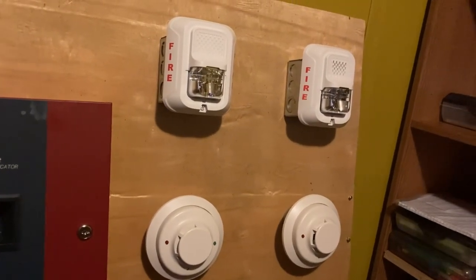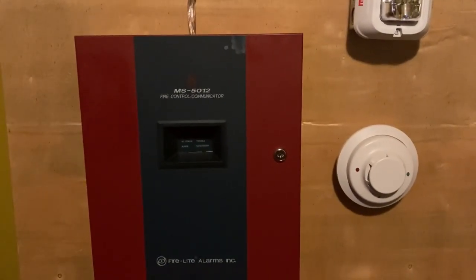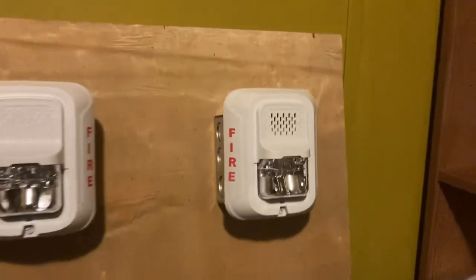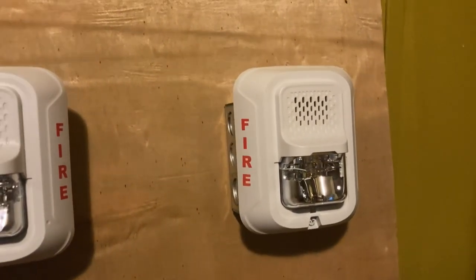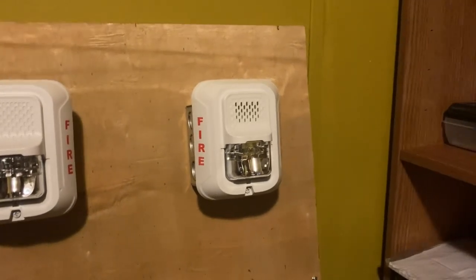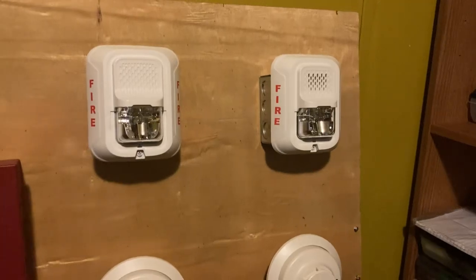Hello everyone, we're back to another video. Today we're going to be doing a system test with the Fire-Lite MS-5012. This fire alarm right here is a System Sensor P2WL horn strobe. Its candela setting is 15 candela and the tone is going to be on Temporal 3, which sounds like a smoke alarm.